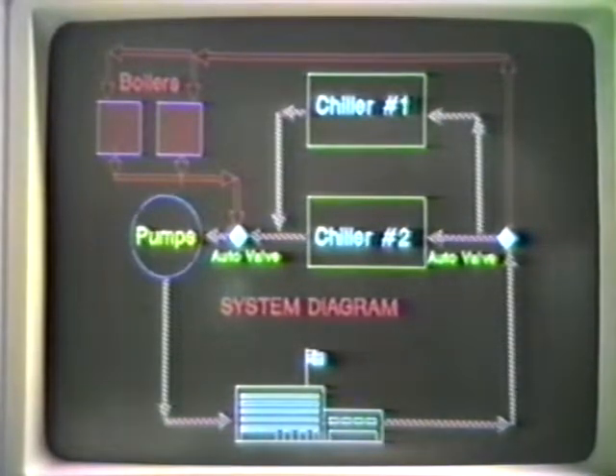Each chiller has its own unit operating panel, which is located on a system panel inside the control circuit section of the access cabinet of the chiller. On this panel are the various service switches and fuses for control of the unit's compressors, fans, control circuits, etc., including the unit's main service switch, which starts or stops the chillers. These switches and fuses are described thoroughly on pages 7 and 8 of the operating and maintenance manual. Also included on this panel is a convenience outlet plug for using plug-in 120-volt tools, lights, and so forth.